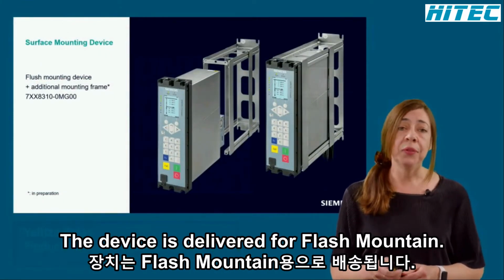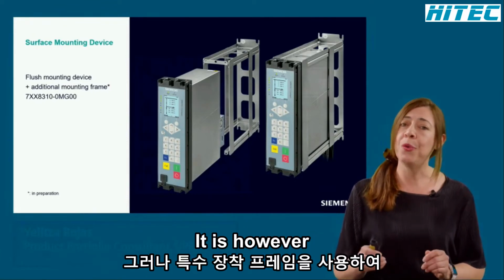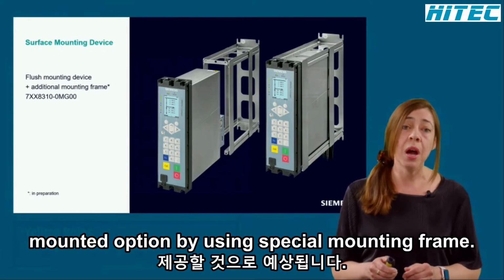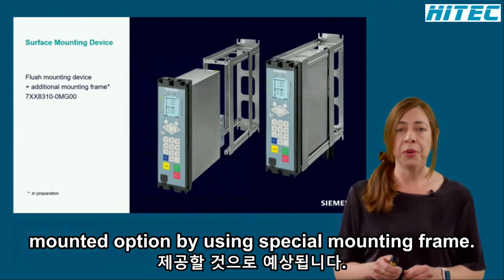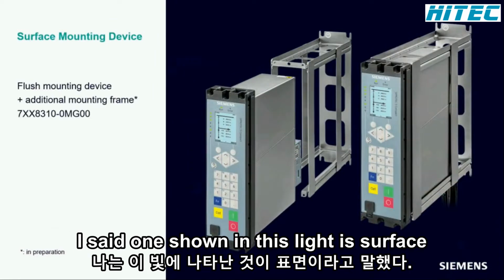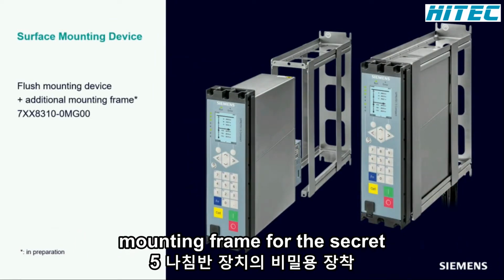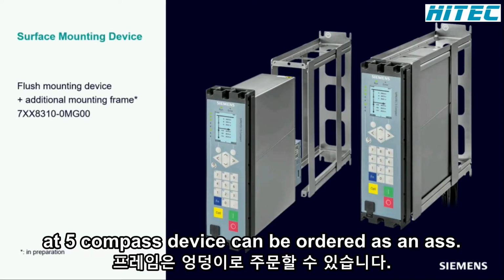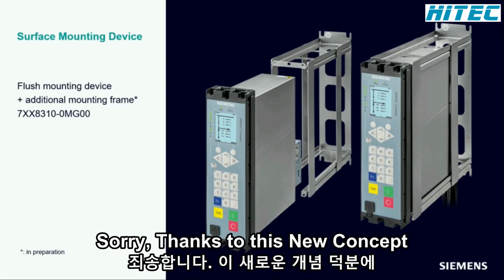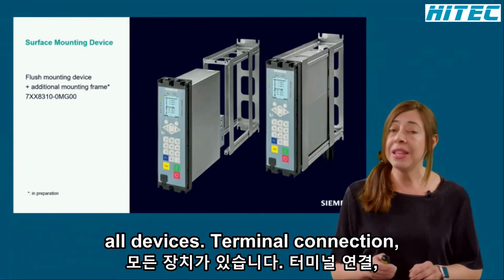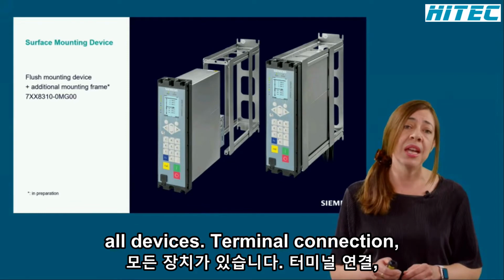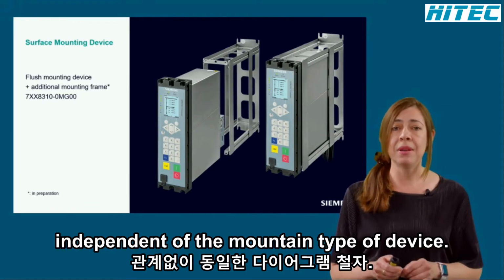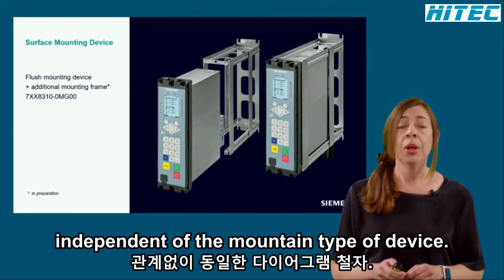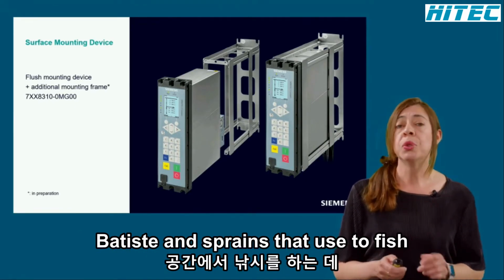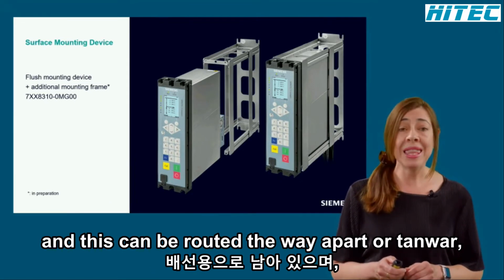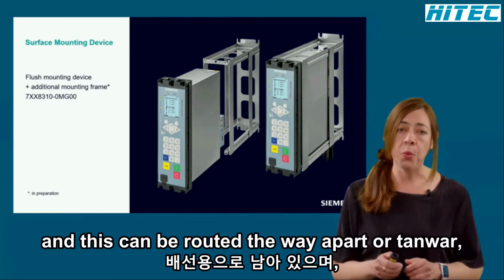The device is delivered for flush mounting. It is, however, foreseen to give the surface mounting option by using a special mounting frame, as the one shown in the slide. This surface mounting frame for the SIPROTEC 5 Compact device can be ordered as an accessory to install it on the wall. Thanks to this new concept, all devices have terminal connection diagrams that are identical, independent of the mounting type of the device. With the distance frames that are used, sufficient space remains for the wiring, and this can be routed away upward or downward. You decide.